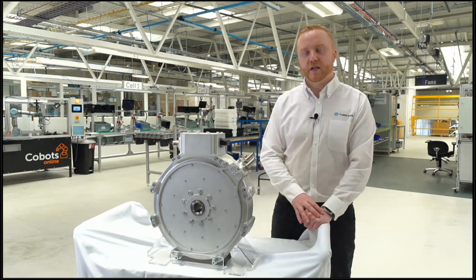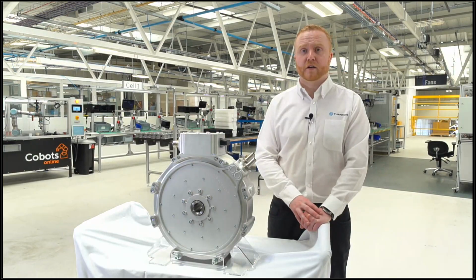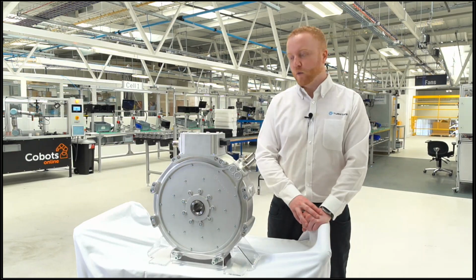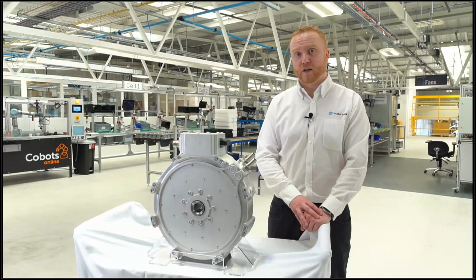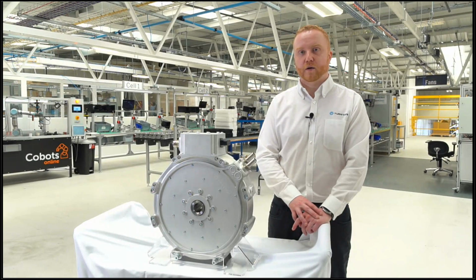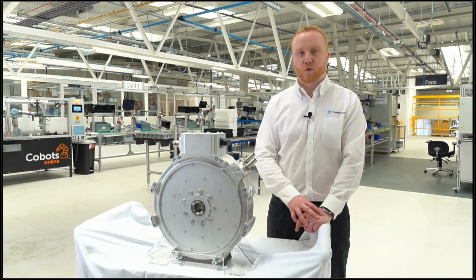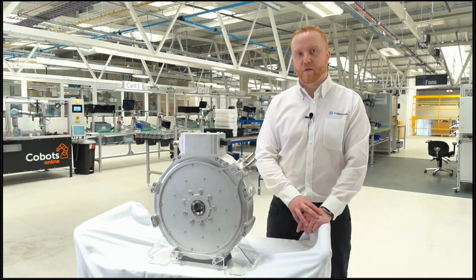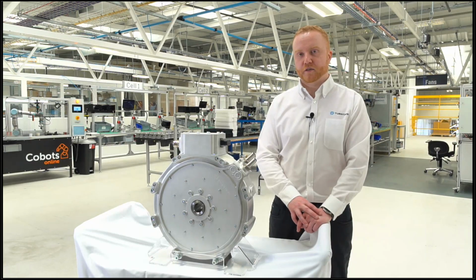From the heat map generated, we first looked at correlation to our thermal models, since we're always keen to develop them further. What we found is that the highest temperature point was in the end windings at the outer, close to the phase cable exits, which is the location we put the sensors into. That's controlled during the winding process and drawing to ensure the temperature sensor is embedded in the same location, or within tolerance, every time.